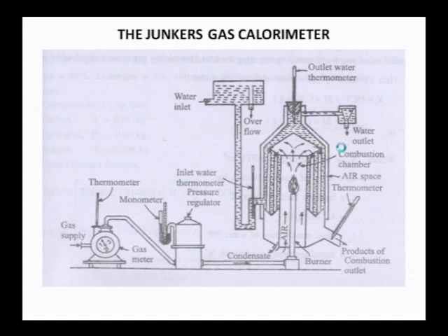One is the water tube, another is the gas tube, the flue tube. In a flue tube, hot gases are flowing. In a water tube, water passes. Both water and gas move in the opposite direction. There is a water inlet.